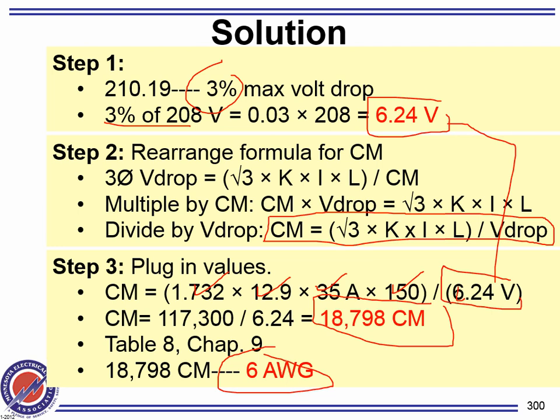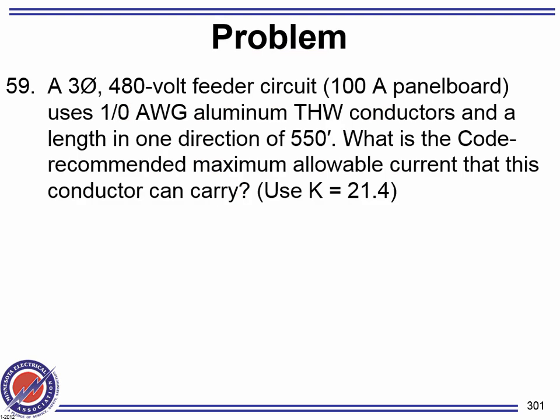Okay. One more example. We have a 3-phase 480. The panel is 100 amp. It's 1/0 aluminum. The distance is 550, and K is given this way, and we need to find the allowable amp. They're giving you an amp of a panel. Remember, you're not looking at panel's amp. You're looking at what? Load's amp. So you need to flip the formula to get you the amp, right? We've done that.